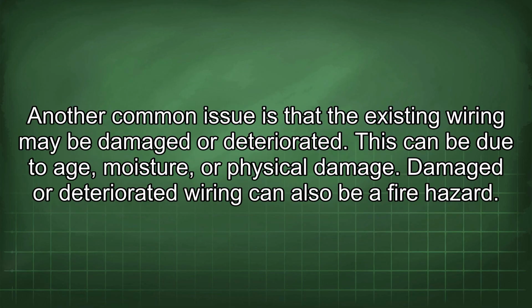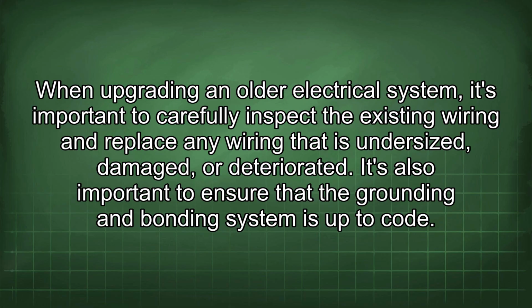Another common issue is that the existing wiring may be damaged or deteriorated. This can be due to age, moisture, or physical damage. Damaged or deteriorated wiring can also be a fire hazard. When upgrading an older electrical system, it's important to carefully inspect the existing wiring and replace any wiring that is undersized, damaged, or deteriorated. It's also important to ensure that the grounding and bonding system is up to code.